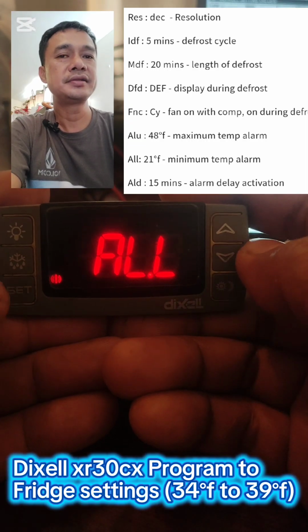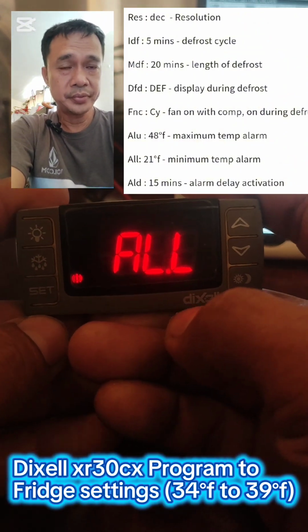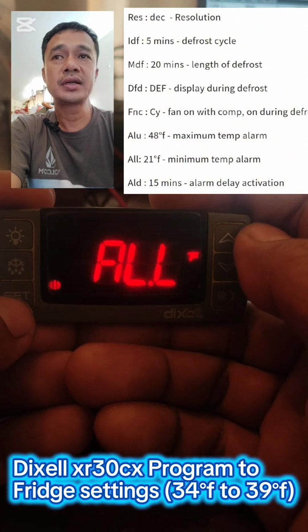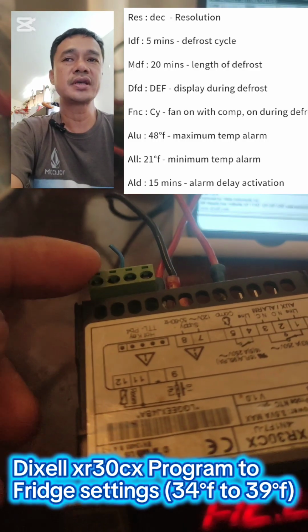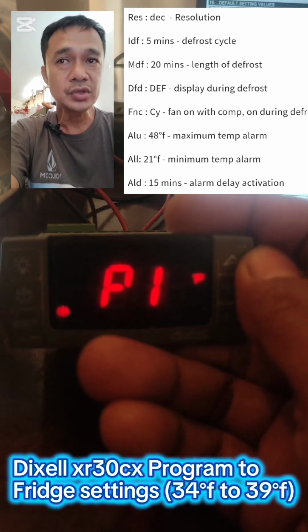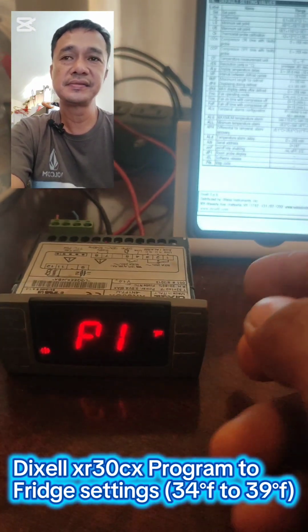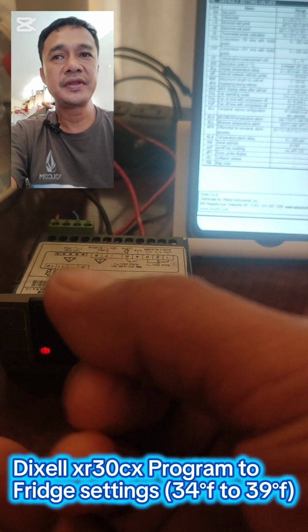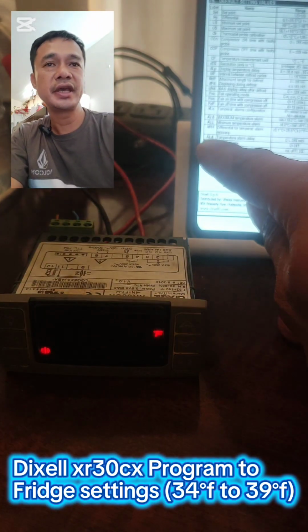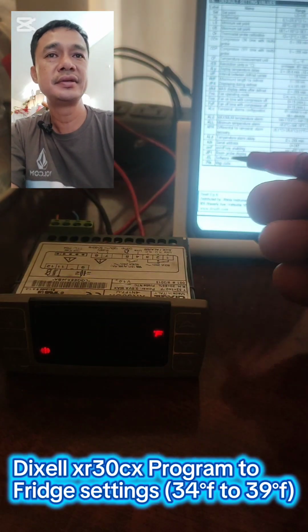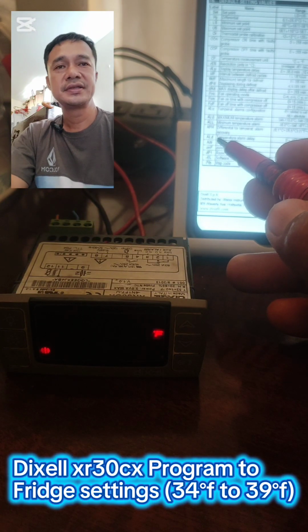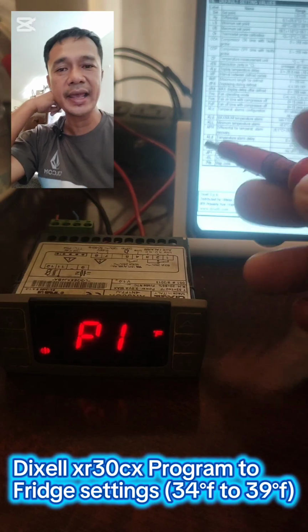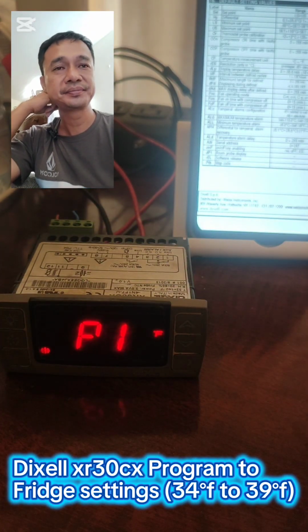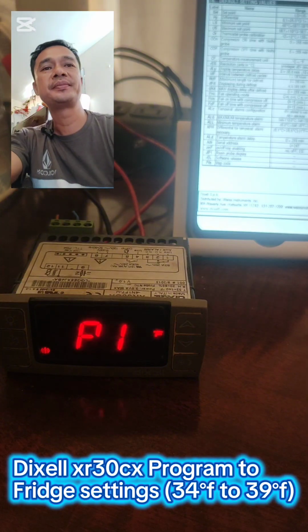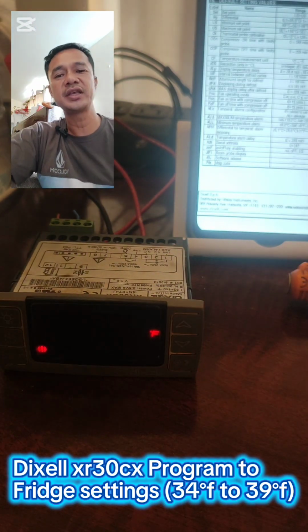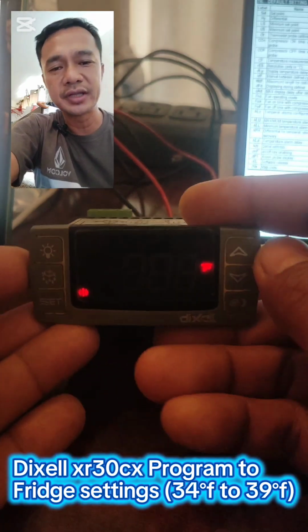And for the ALL, the minimum temperature alarm, just in case our set point is 34 degrees Fahrenheit and we have a problem with the sensor, it goes to 21 degrees Fahrenheit. Then a 15 minute delay, which is the ALD parameter. Once the 15 minutes is up, then an LA alarm shows up. And if it has a buzzer, it will keep on buzzing. And it will call the attention of the technician.